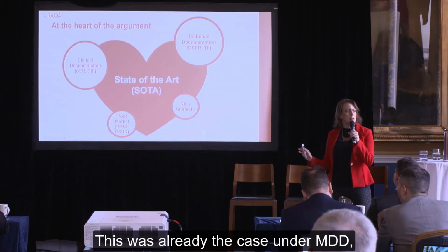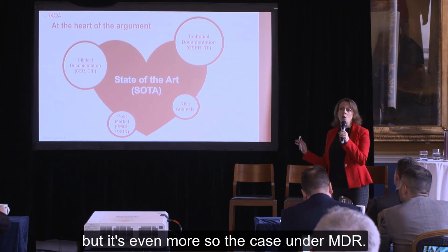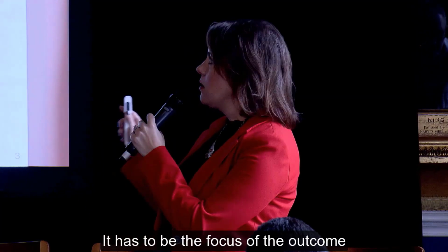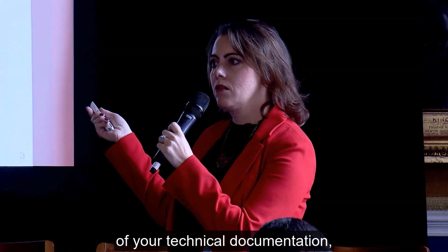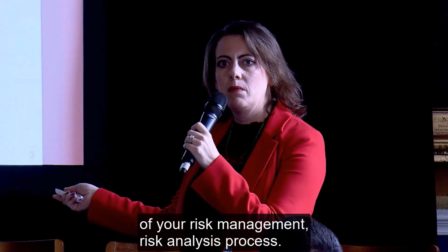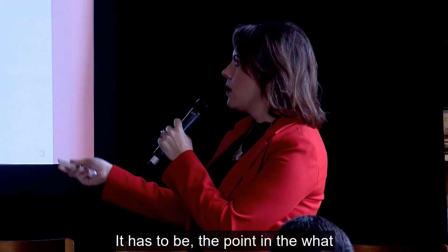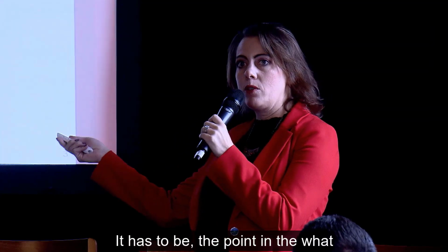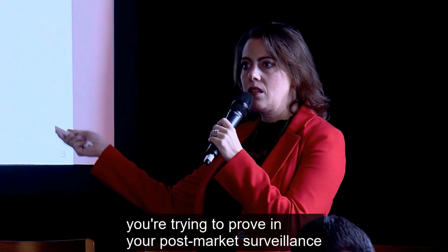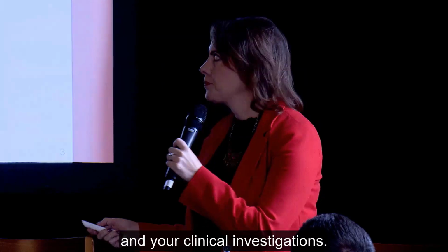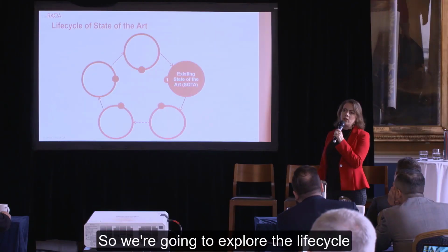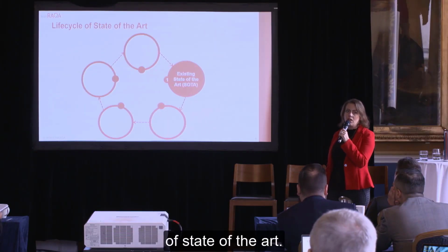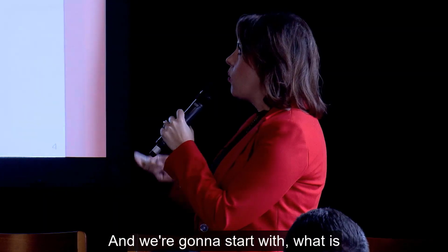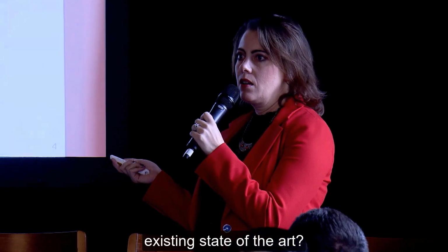This was already the case under MDD, but it's even more so the case under MDR. It has to be the focus of the outcome of your technical documentation, of your risk management, risk analysis process. It has to be what you're trying to prove in your post-market surveillance and your clinical investigations. So we're going to explore the life cycle of state of the art, and we're going to start with what is existing state of the art.